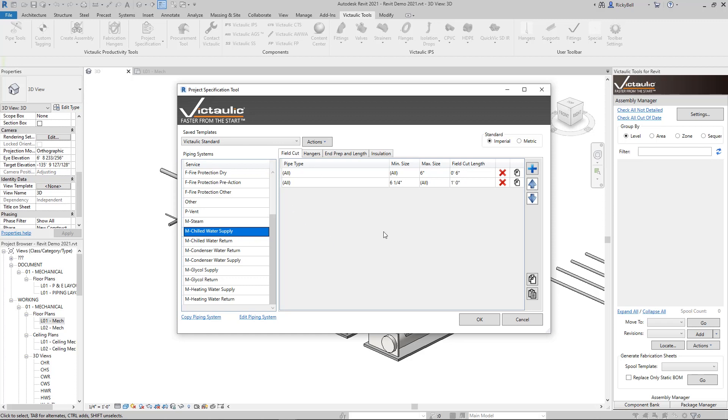Let's take a look at some of the common piping systems here under Chilled Water Supply. Under Field Cuts I have some rules in here that say regardless of the pipe type and from any sizes up to six inch, I want to have a six inch field cut length added to any field cut designated pieces of pipe. Beyond that, six and a quarter inch and up, I'd like it to be a foot. So these rules that I have in here for field cut are pretty basic.